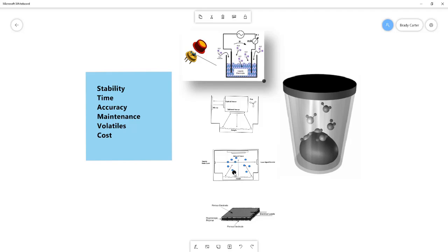and then the saturated vapor pressure based on the sample temperature, and the two together give the relative humidity or water activity. And a tunable diode laser has a laser tuned to a wavelength that's specific to water, which can then measure vapor density inside the chamber, which then relates to vapor pressure, and also measures the sample temperature to get the saturated vapor pressure. So all these different methods measure in some way or another the relative humidity inside this chamber. But none of them measure it directly in the sample. So none of them is a direct measurement of water activity. Instead, all methods depend on measuring the headspace that's at equilibrium.